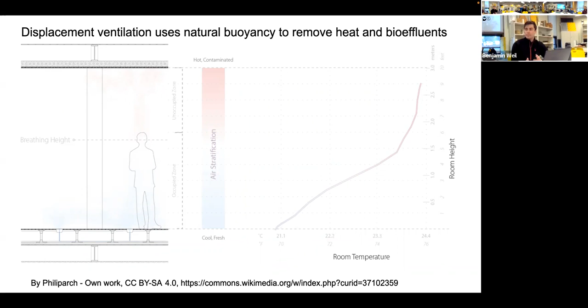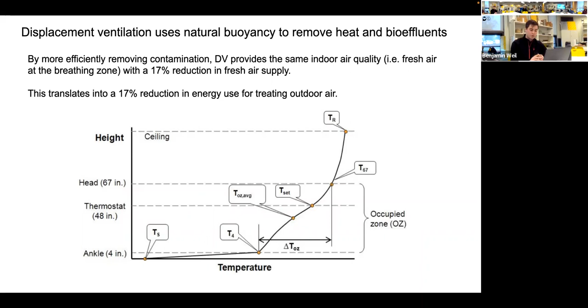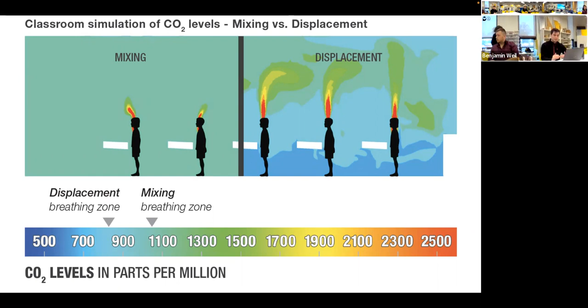Removing heat using its natural buoyancy, displacement ventilation provides a 17% reduction in fresh air supply, which also translates to 17% reduction in energy use. This picture shows a simulation of how displacement is better than mixing. Carbon dioxide is a good indicator for airborne pollutants such as viruses and bacteria. And this picture shows that when you mix the air, you are also mixing everything else too. Displacement makes it so any polluted air rises more quickly out of the breathing zone.